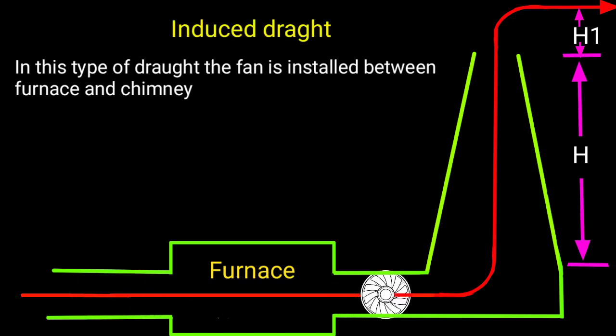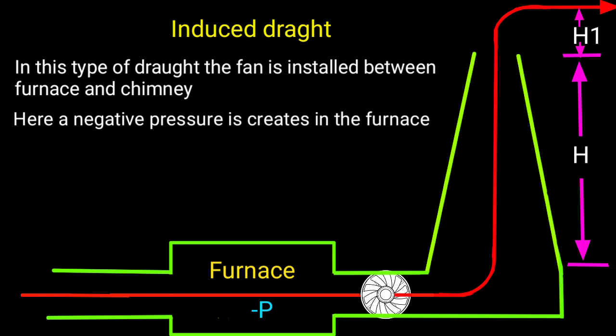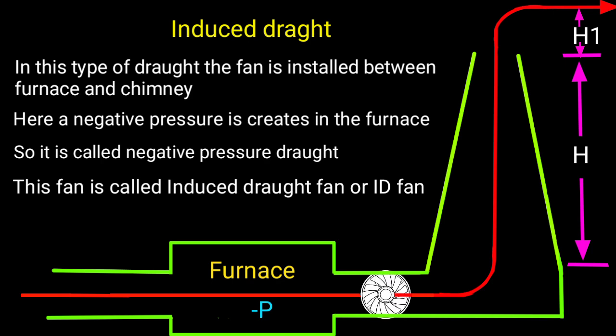Induced draught. In this type of draught, the fan is installed between furnace and chimney. Here, a negative pressure is created in the furnace, so it is called negative pressure draught. This fan is called induced draught fan or ID fan.